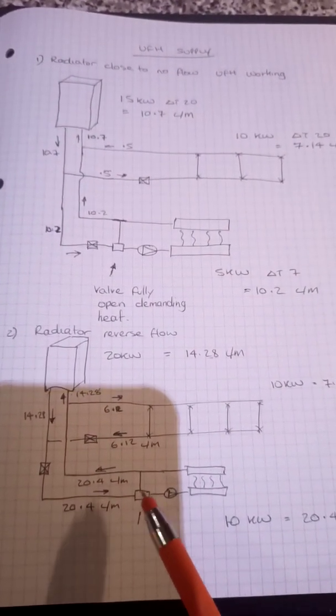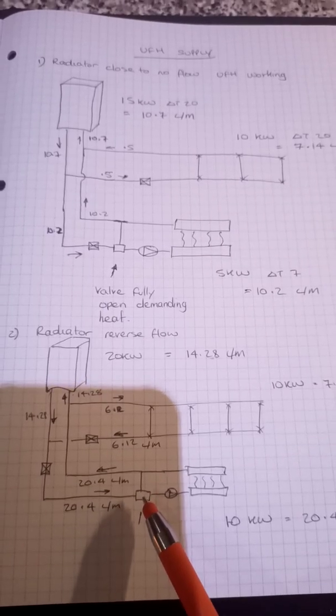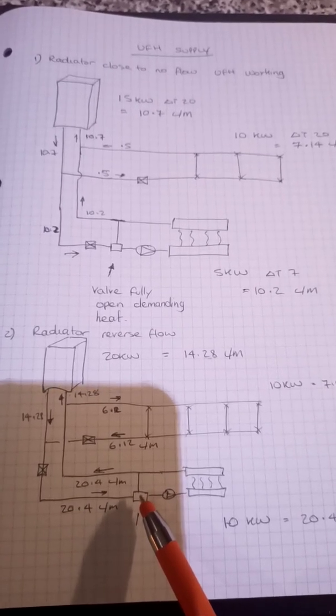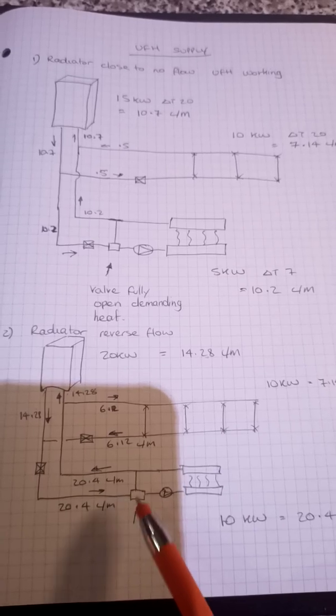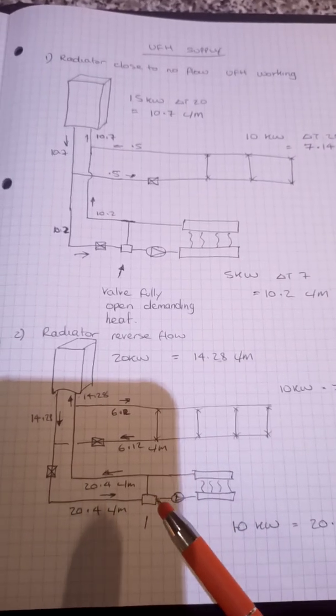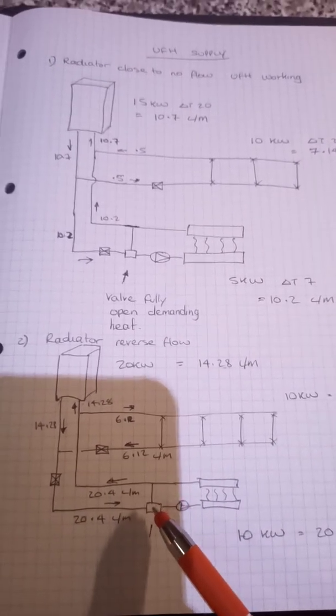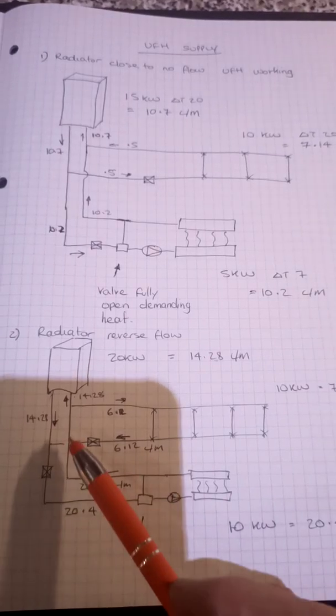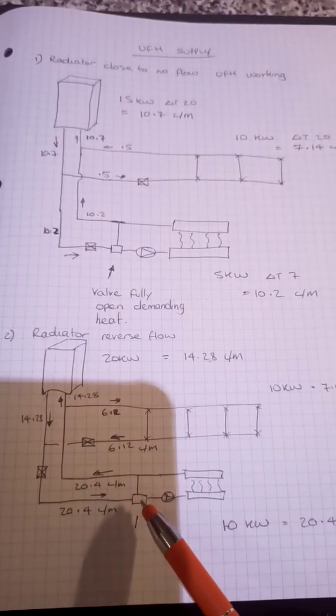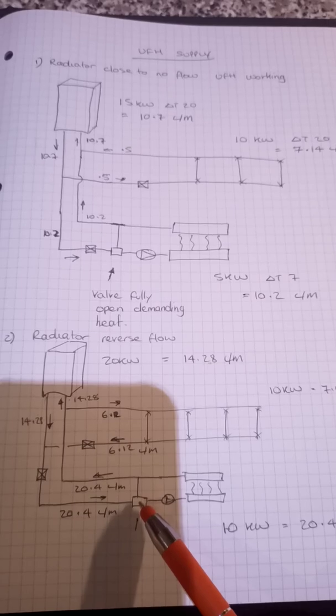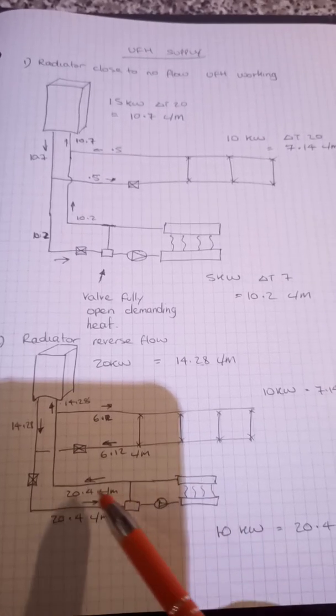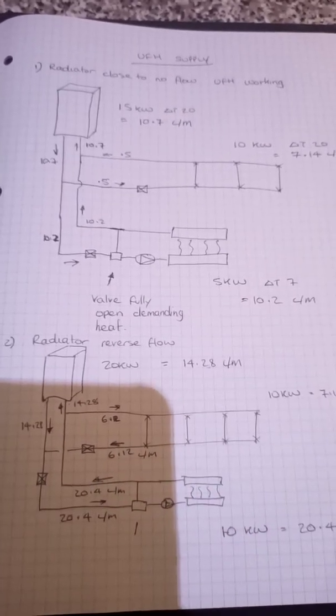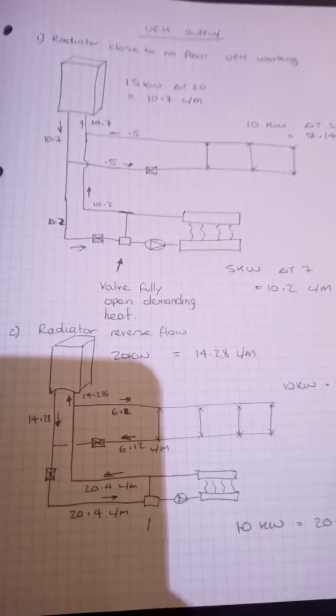In effect, a lot of these valves from the manufacturers will state that they require a minimum temperature arriving at them, which I think is 70 degrees. I won't argue with anyone if they tell me that's not quite right, but I believe it's 70. So we're supplying a temperature in here, maybe 40. Valve's not going to close. It's looking for 70. Full flow round, and we starve these radiators. And the cure is simple.